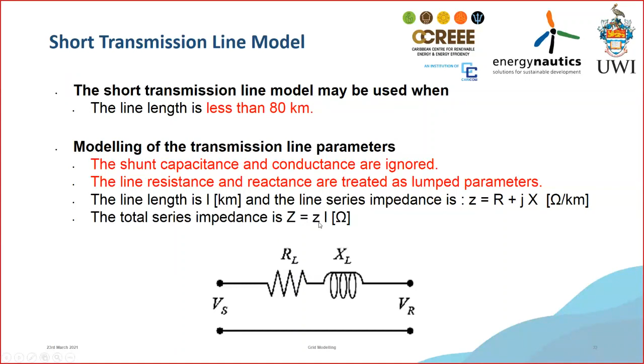In terms of my medium line transmission, which is between 80 to 250 kilometers, I now have to take into account the inherent capacitance between the conductors. This capacitance is now represented by the lump admittance between the sending end and the lump admittance at the receiving end of my particular line. This is how we get the actual line model, but this R and X would have come before from whether my system is bundled, what is the formation, etc.